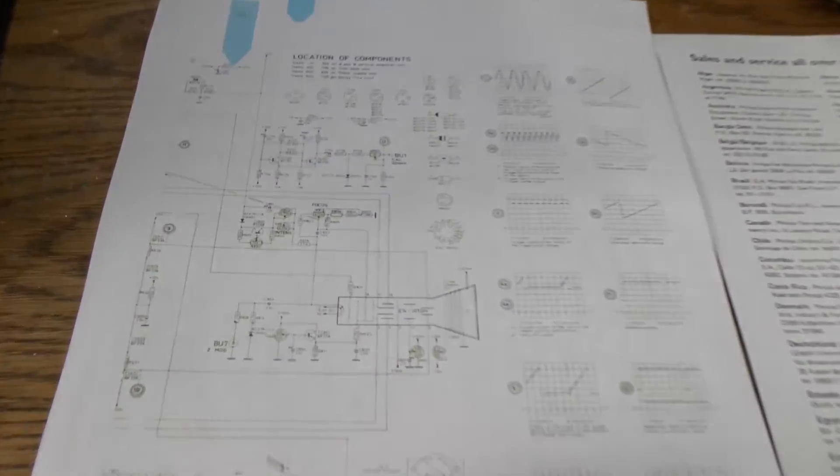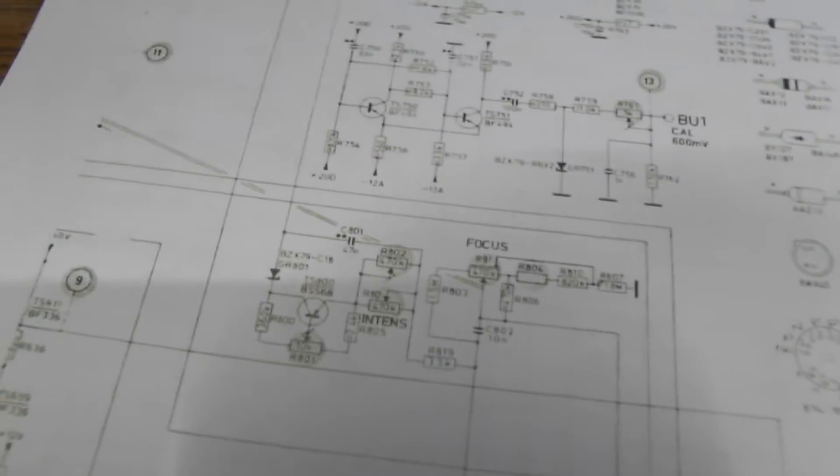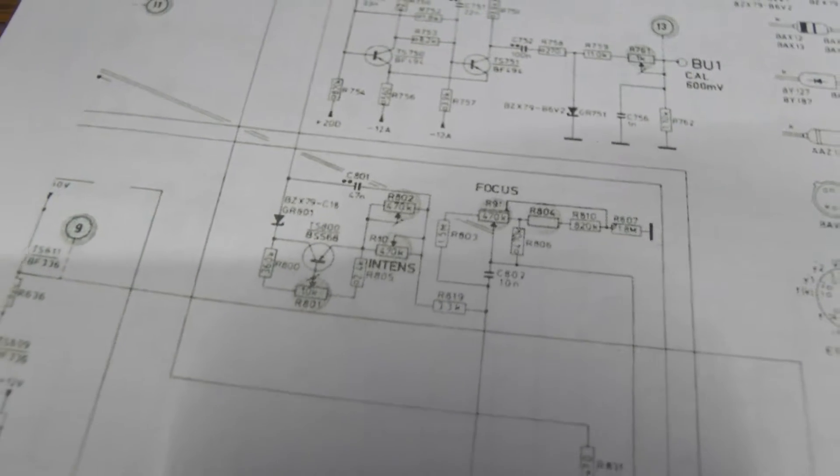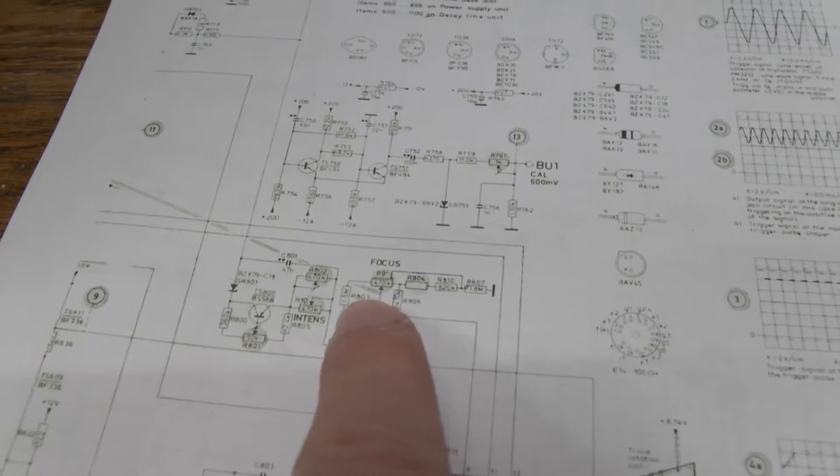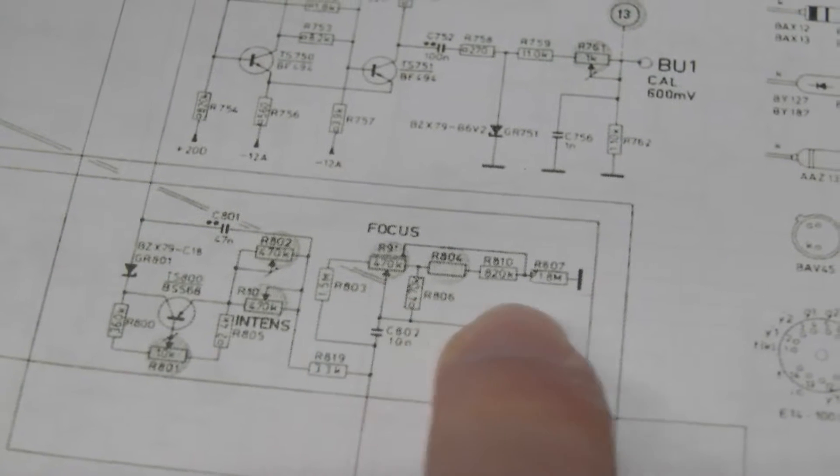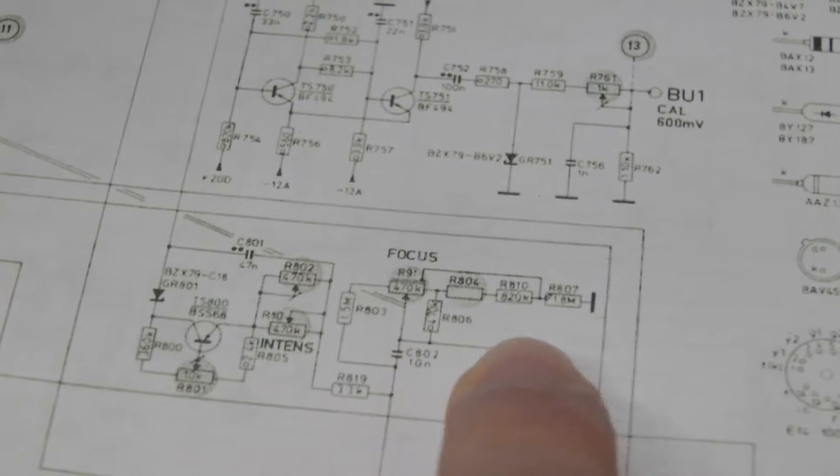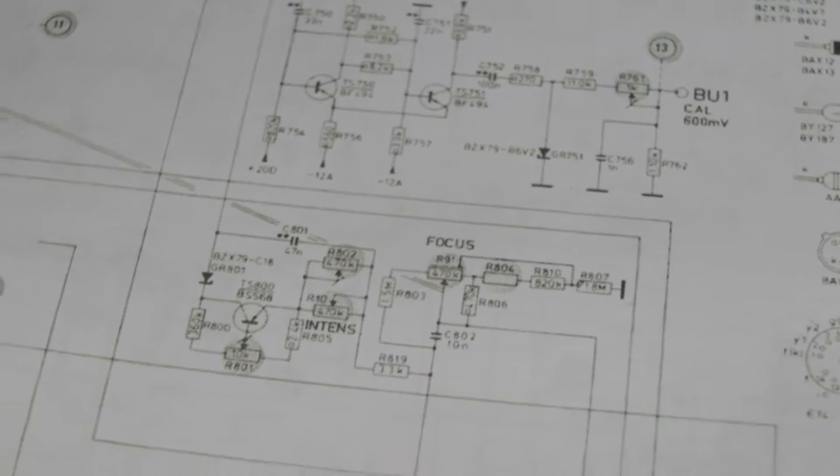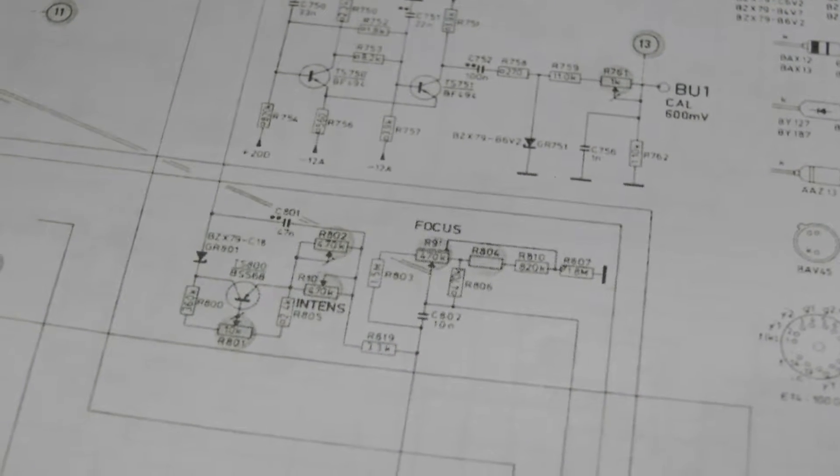And apparently it all comes down to a part of the circuitry which does the focus, and it seems like some of the resistors in this circuit like to drift. They go out of tolerance and eventually cause a problem.